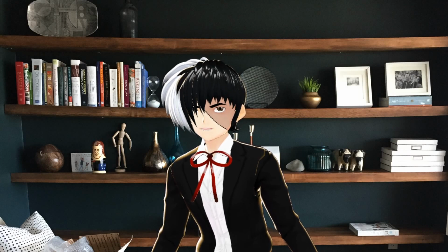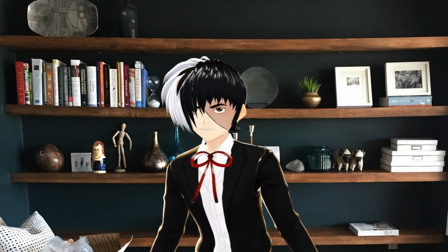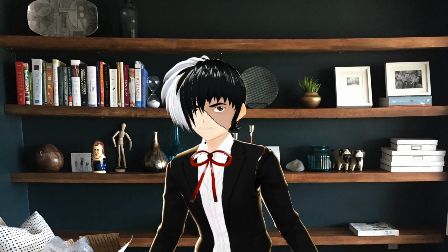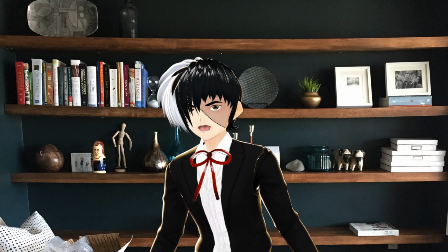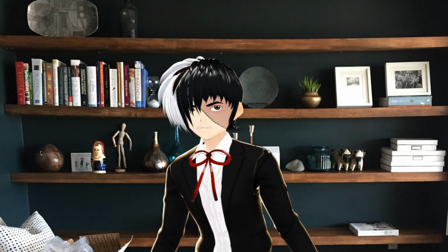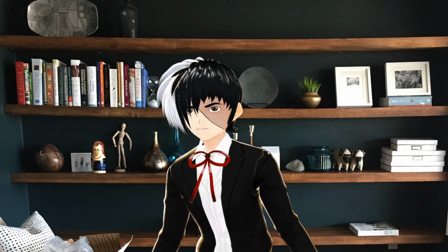When using a manual defibrillation paddle, make sure that the paddles are either on the defibrillator cradle or on the patient's chest with minimal time in transit from one position to the other. To prevent inadvertent discharges, always point the paddles downward and never wave the paddles around or face them toward each other, especially when charged. This is to prevent inadvertent discharges or sparking.